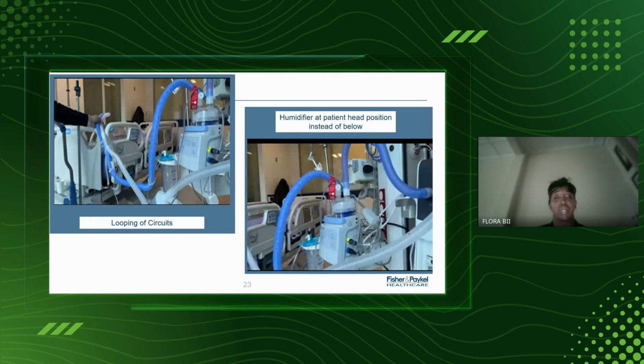Looping of circuits, for example. When a circuit is looped in this manner, you'd have mobile condensate that can form in the loop. So in conjunction with the nurses, and it is very important that the nurses understand this, they would need to position the humidifier much lower than the patient's position, preferably at the bottom, so that by gravity that excess condensate rains out and falls back into the humidification chamber.